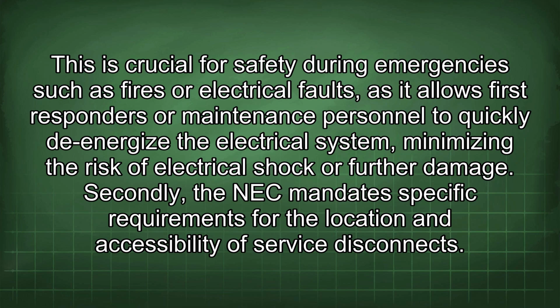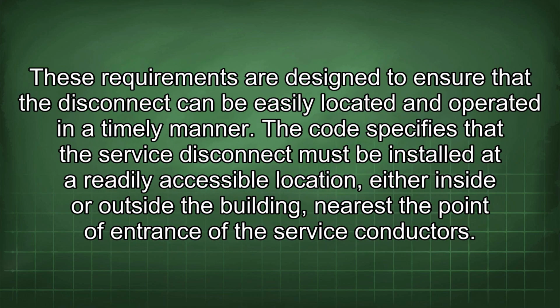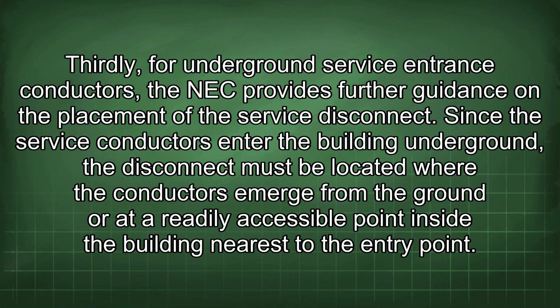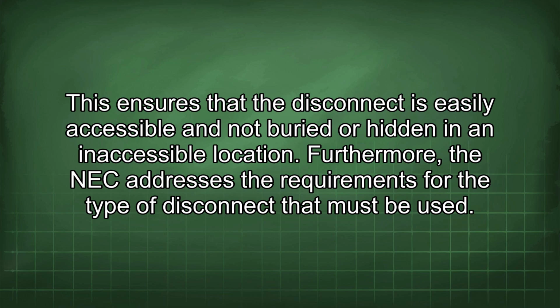Secondly, the NEC mandates specific requirements for the location and accessibility of service disconnects. These requirements are designed to ensure that the disconnect can be easily located and operated in a timely manner. The code specifies that the service disconnect must be installed at a readily accessible location, either inside or outside the building, nearest the point of entrance of the service conductors. Thirdly, for underground service entrance conductors, the NEC provides further guidance on the placement of the service disconnect. Since the service conductors enter the building underground, the disconnect must be located where the conductors emerge from the ground or at a readily accessible point inside the building nearest to the entry point. This ensures that the disconnect is easily accessible and not buried or hidden in an inaccessible location.